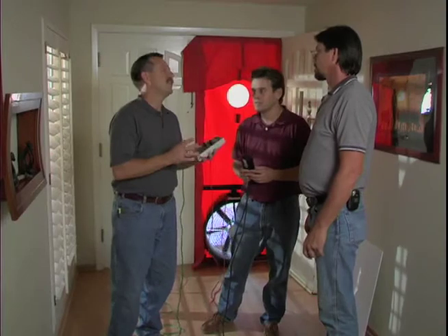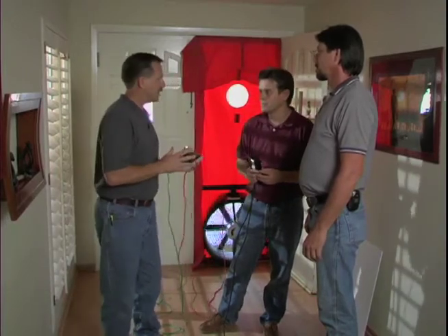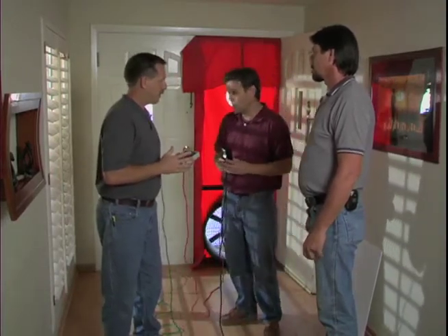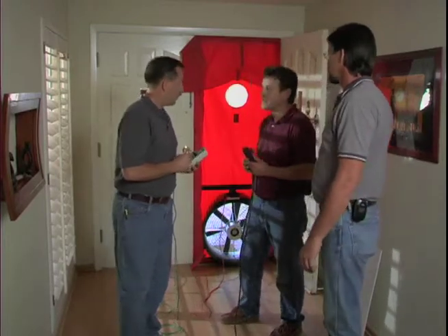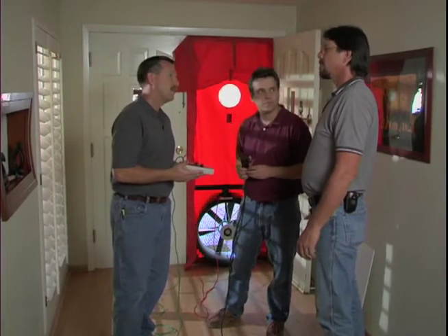You know, let's make clear what we're doing here. We're pressurizing the whole house, right? Yes. What we're doing is with this fan, we're forcing air into the house to reach a certain pressure. And the amount of air that it takes to reach that pressure tells us how leaky the house is. Okay, what is that 4,800 CFM in easy to understand terms? That's about a 470 square inch hole to the outside.